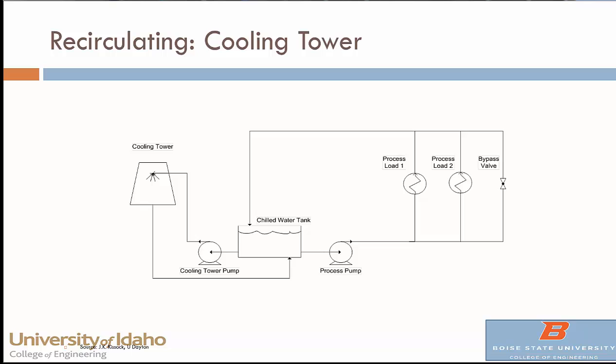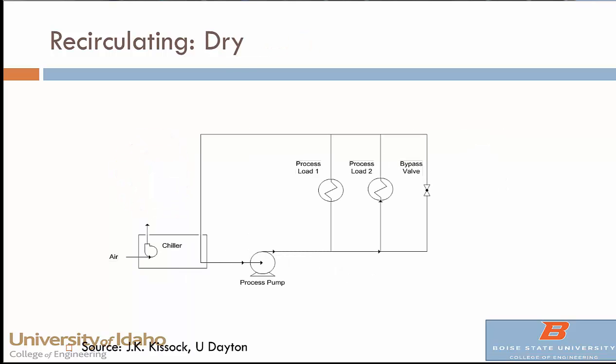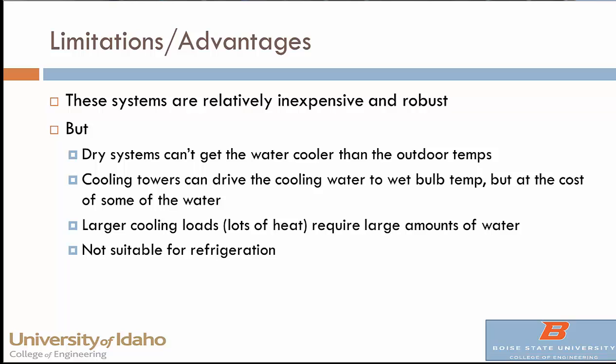More common are various kinds of recirculating systems. Here, chilled water comes from a tank through various machines and devices in the plant, and then as it warms up, it's pumped out to an outside cooling tower. You could also use a chiller or an air-driven cooler outside — called a fluid cooler — where all the working fluid stays within a closed system. These are relatively inexpensive and robust.